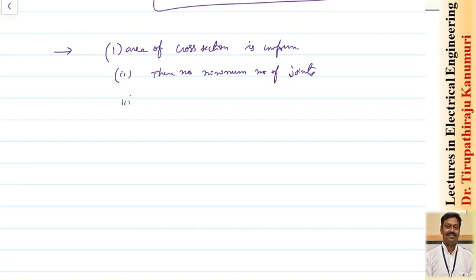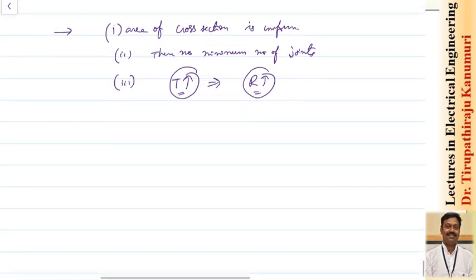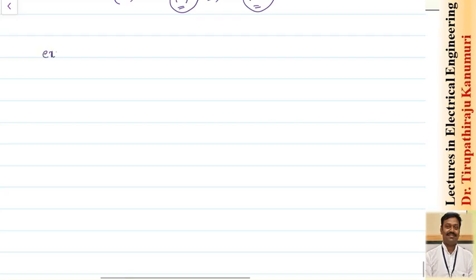And the third one, when the cable temperature increases, the resistance increases or decreases depending on the temperature. So the effect of temperature also should be considered while making these calculations so that errors will be avoided. This care should be taken while applying the Varley loop test or the Murray loop test. So let us take one example so that this method will be completely clear to you.